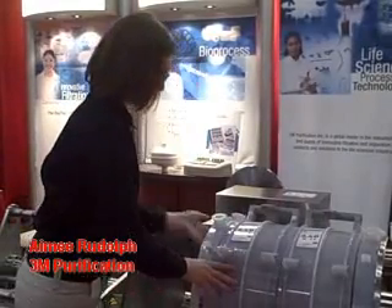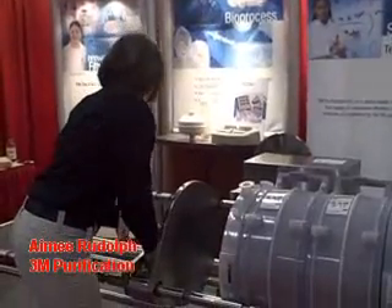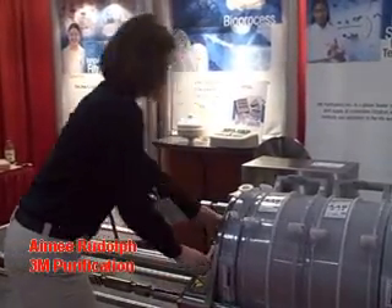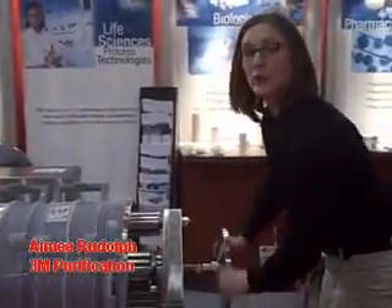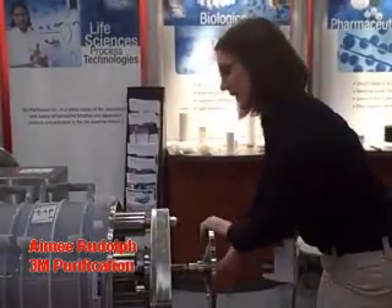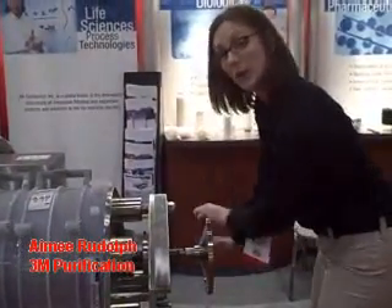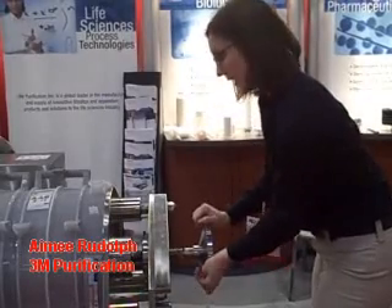Now these two are completely connected. Your top manifold is also a press fit. This is used to compress the stack. On this holder, this wheel is torque limiting so it will tighten to the correct tension — it won't over-tighten and you can't under-tighten.